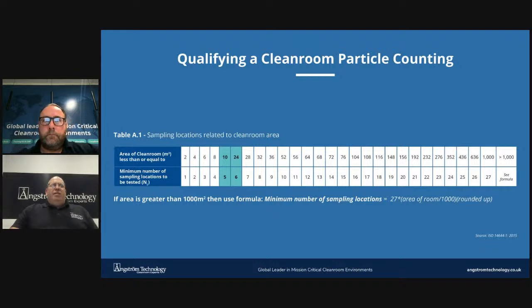The sample time for each location is determined by the ISO class the room is designed to and the largest particle size tested. A lot of the current particle counters sold today have this information pre-programmed into them, and if they are set up correctly by the engineer, can efficiently display the required information to the user.